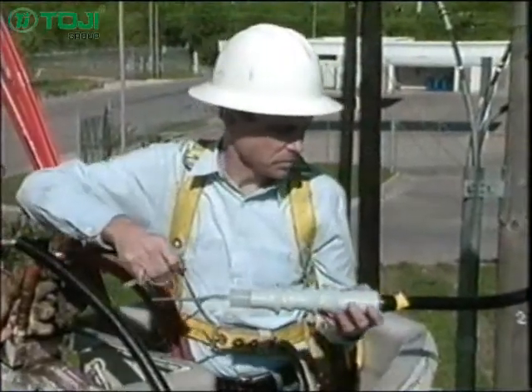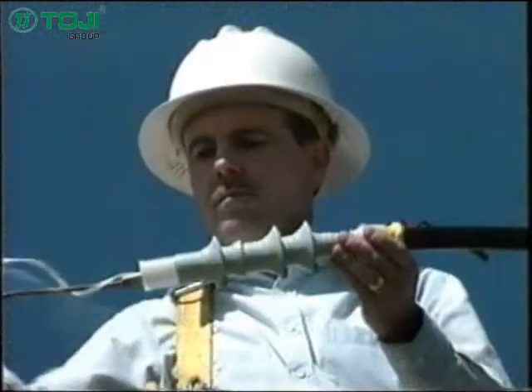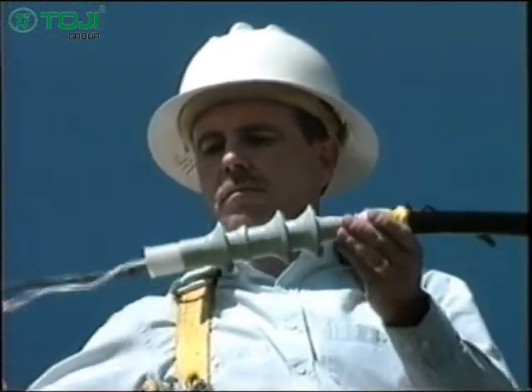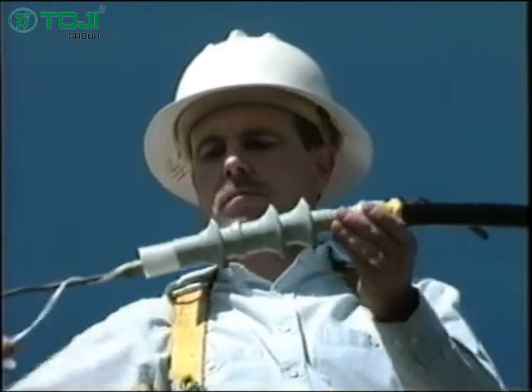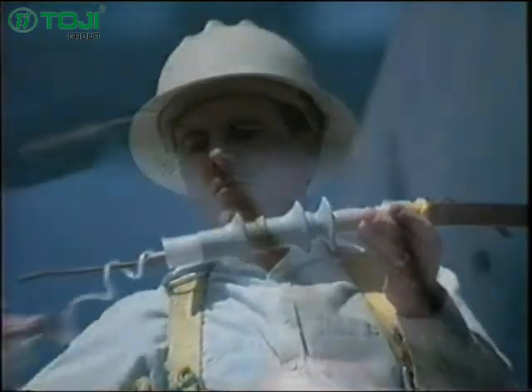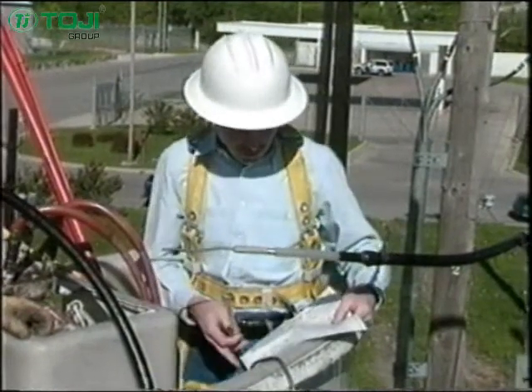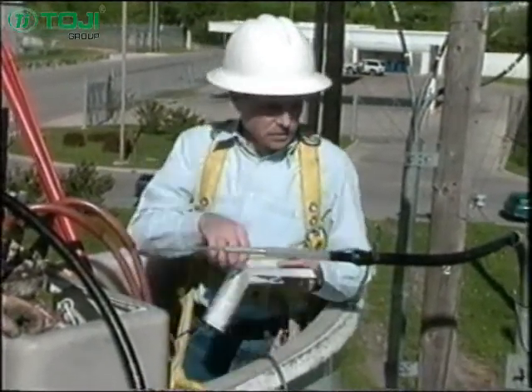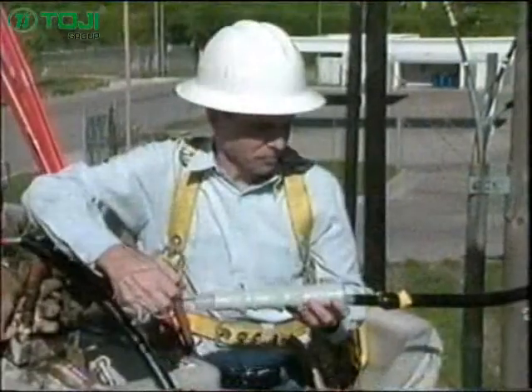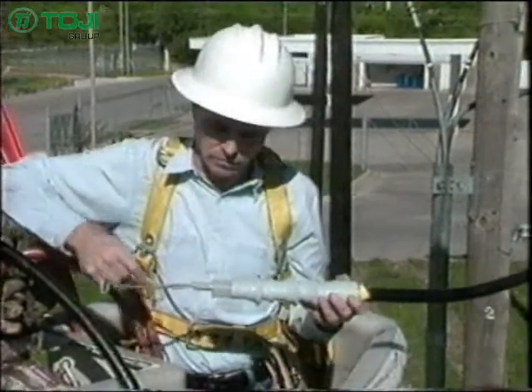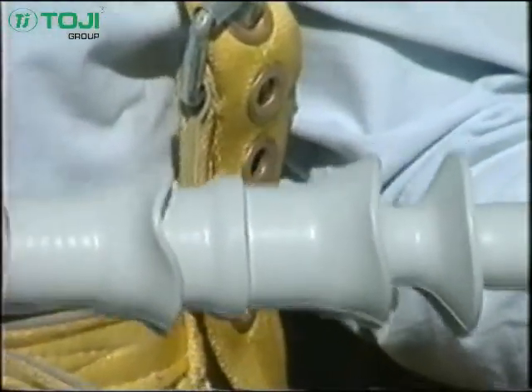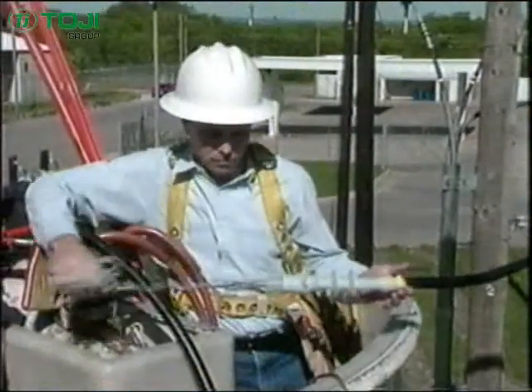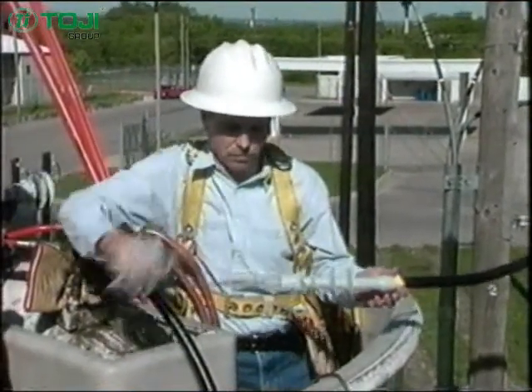Another real advantage to 3M ColdShink skirted silicone Quick Term 2 termination kits is the ease of installation. All QT2 terminations can be installed quickly and easily without bulky stress cones, hot melt adhesives, dangerous torches, or complex tools. Simply prepare the cable according to standard procedure. Install the ground connection and terminal lug. Then seal the ground connection. Place the QT2 termination over the cable and unwind the core. This allows the termination to shrink into place, giving you a complete IEEE 48 Class 1 termination.